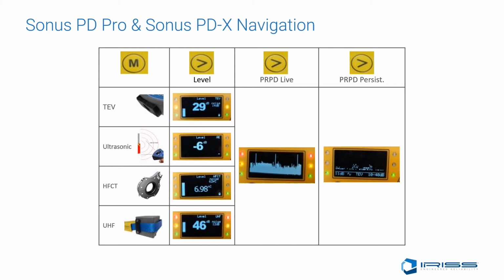The second screen is the live phase resolved partial discharge, or better known as PRPD, live measurement screen. This screen will display each partial discharge as it occurs, giving the user a defined block of amplitude as each of the occurrences discharges. The third screen is the data that was accumulated in the first and second screens.